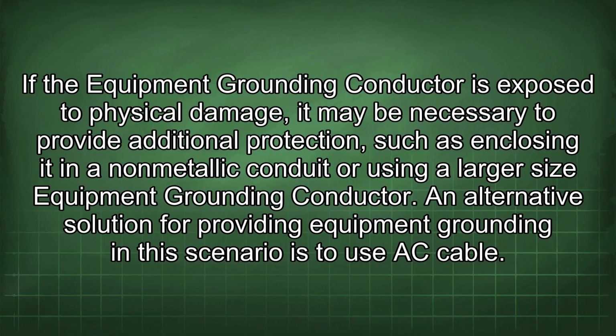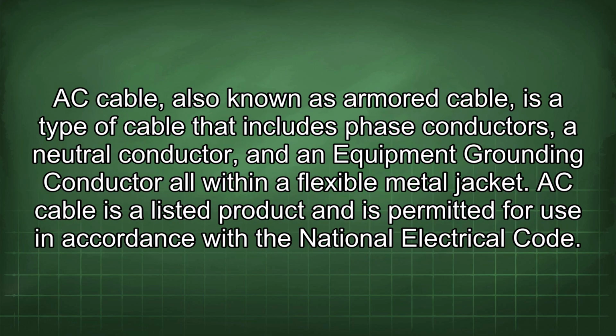If the equipment grounding conductor is exposed to physical damage, it may be necessary to provide additional protection, such as enclosing it in a non-metallic conduit or using a larger size equipment grounding conductor. An alternative solution for providing equipment grounding in this scenario is to use AC cable. AC cable, also known as armored cable, is a type of cable that includes phase conductors, a neutral conductor, and an equipment grounding conductor all within a flexible metal jacket.